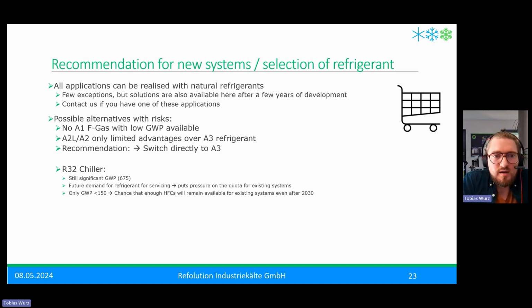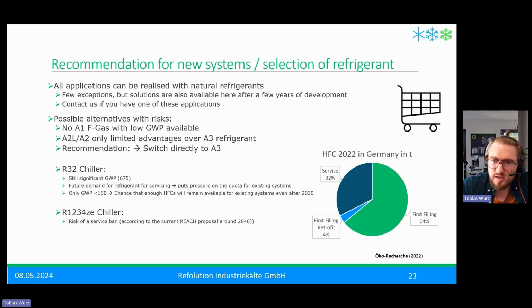For example, the R32 chillers still have a significant GWP. And why I mention it here: if you now buy this chiller and generate a need for service in the next years to service this chiller, there will be a problem for all the HFC applications that are now in the field and will be in the field around 2030. I brought here a small diagram, a statistic of the consumption of HFC 2 years ago in Germany in tons, just to give you a feeling for this.